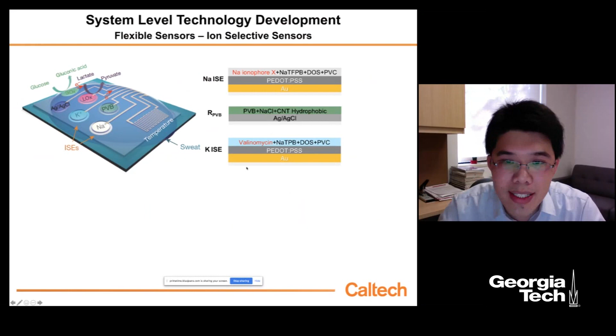If we want to detect ions, let's say sodium, potassium, calcium, or pH, a common way is using ion-selective sensors. Basically, we can modify our working electrode with ion-selective films. For example, if we want to detect sodium, we can prepare a sodium ionophore-containing sodium-selective film. For potassium, we use valinomycin, another chemical selective to potassium. This red text is the ionophore specific to each ion. How do they work? Say we want to detect potassium, we use valinomycin as the ionophore. Valinomycin has a ring structure, and the ring size is similar to potassium ions.